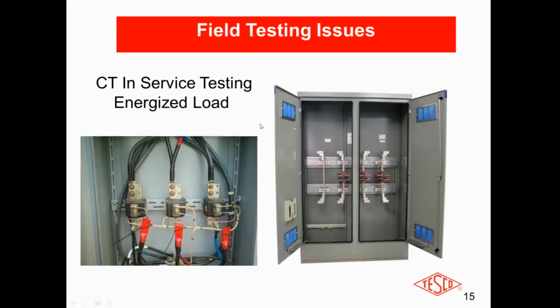This is a very important part of the measurement circuit. If there's anything wrong here, other than catastrophic failure, if there's a measurement problem, an output problem, or worst case, a reverse condition with these two wires, the meter really doesn't know that. More modern meters coming out are getting quite sophisticated, but they're also rather expensive to put everywhere. The point is the meter will just calculate the kW using its constant, and give you the billing and the revenue.